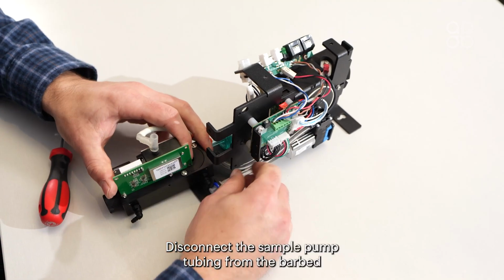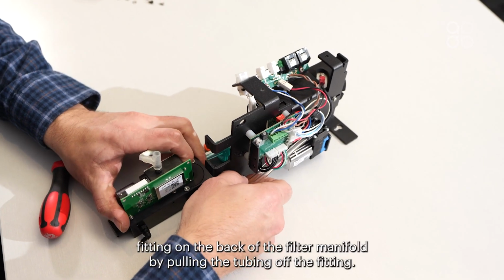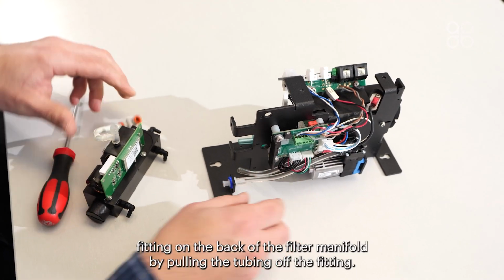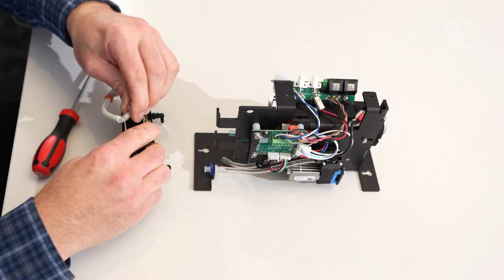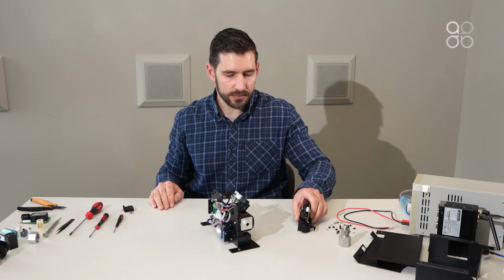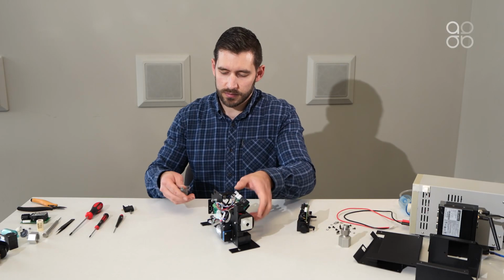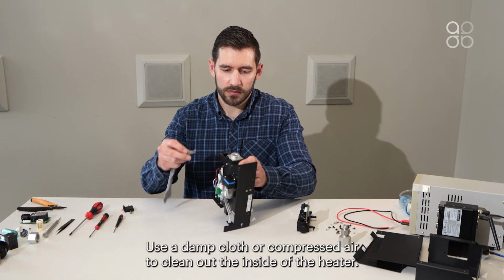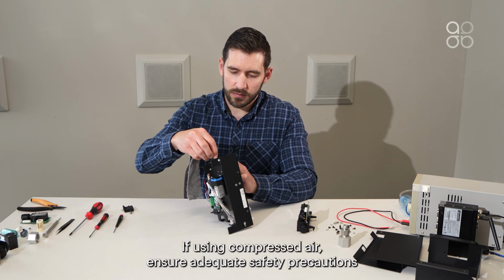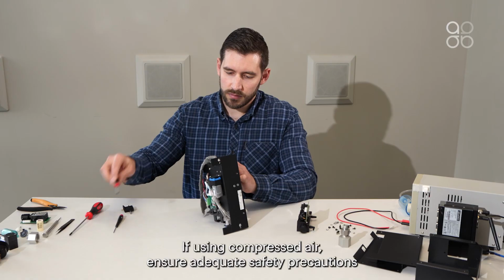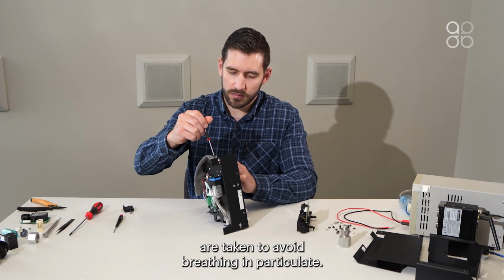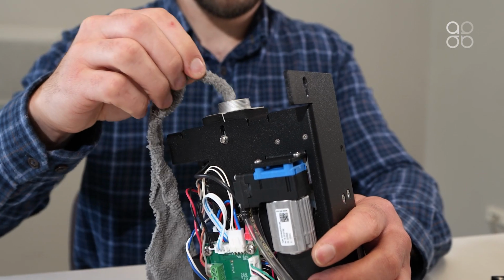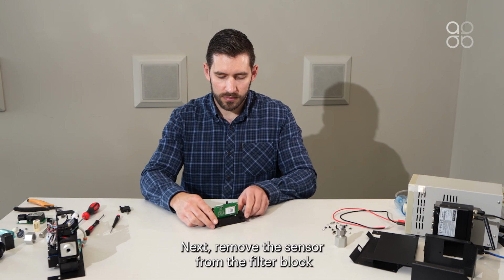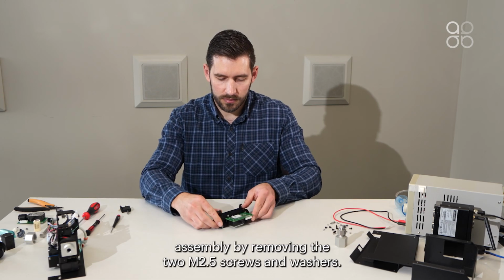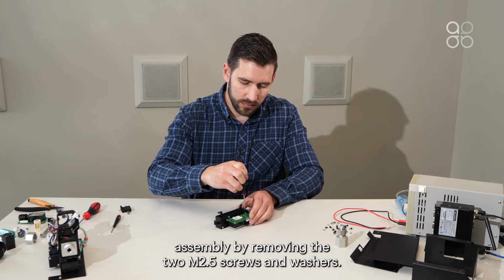Disconnect the sample pump tubing from the barbed fitting on the back of the filter manifold by pulling the tubing off the fitting. Use a damp cloth or compressed air to clean out the inside of the heater. If using compressed air, ensure adequate safety precautions are taken to avoid breathing in particulate. Next, remove the sensor from the filter block assembly by removing the 2 M2.5 screws and washers.